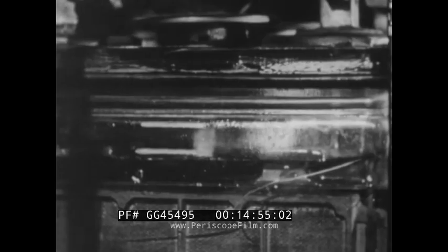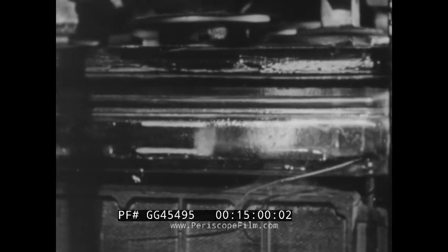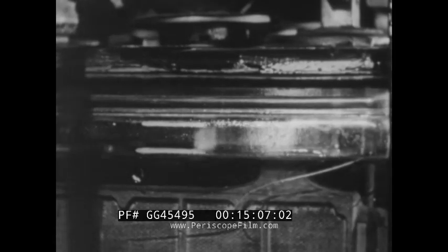Here is a low water condition that, if left uncorrected, will result in deterioration of the exposed plates. When water is added to any battery, use only approved tap water or distilled water.